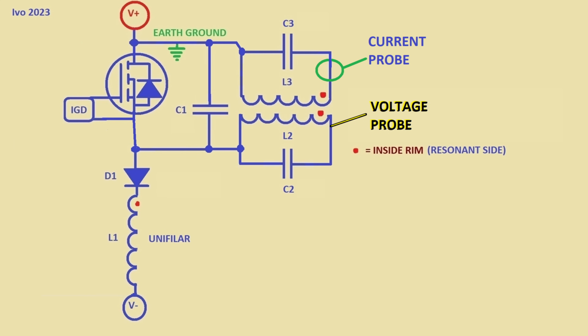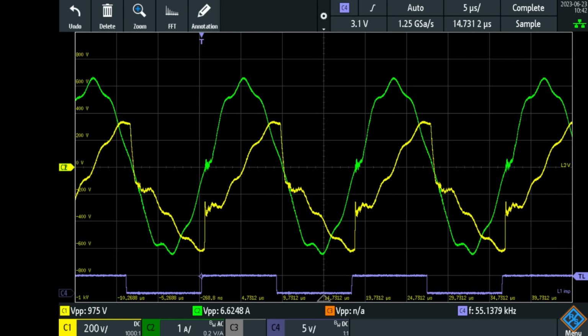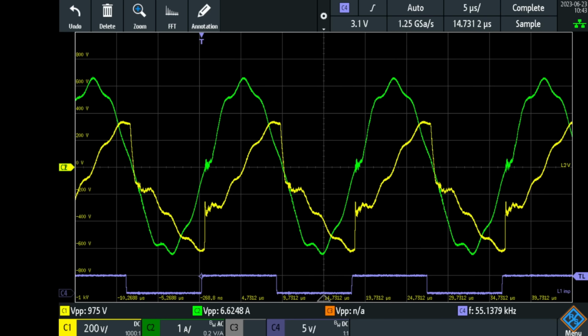So now in yellow we have the L2 voltage, and you might see some similarities between the wobbly current of L3 and the wobbly voltage of L2. There seems to be a correlation between the fluctuations in both those measurements. And this indicates to me that this is actually not a magnetic current that I'm measuring in L3, but actually a displacement current, which is related to the changes in voltage of that coil capacitor. Now the question stays, where does that energy come from?